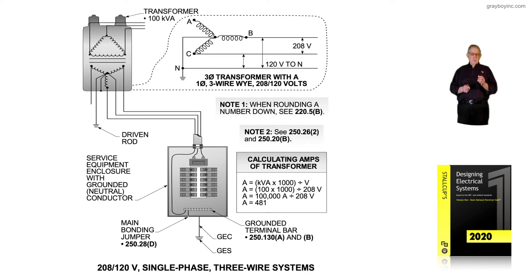Notice that if the transformer is grounded, we have to pull a grounded conductor in regardless. We connect it to the service equipment, and we connect it to earth ground. Note 2 suggests we review 250.26(2), as well as 250.20B, which provides the information we need to know exactly what takes place when we ground the transformer, ground the service, and bring in a grounded conductor capable of carrying fault current if such a condition should occur.